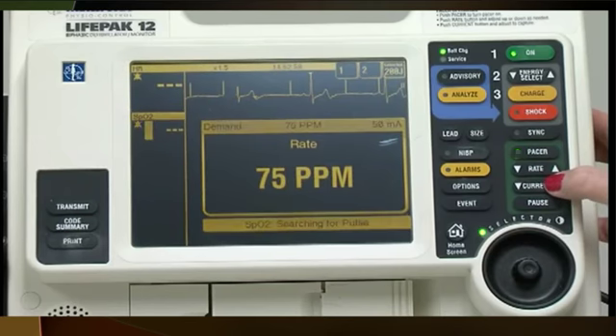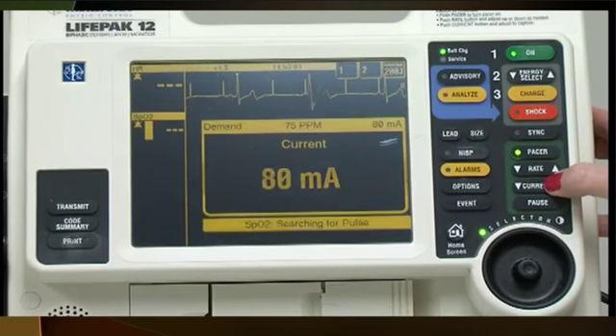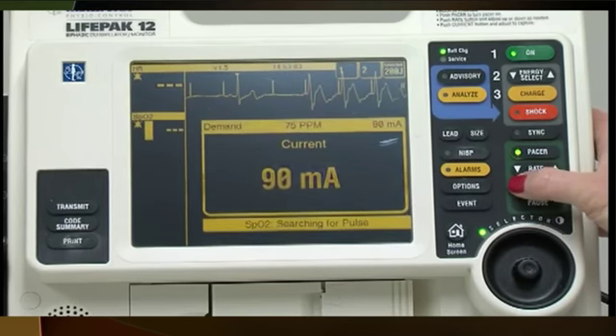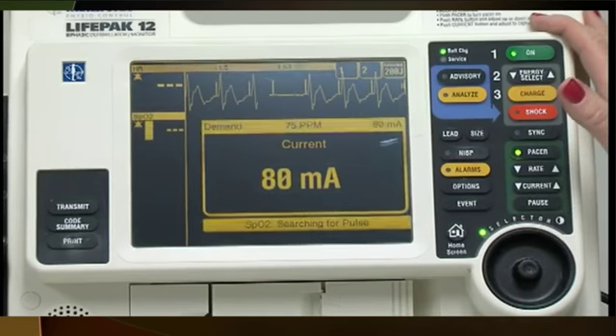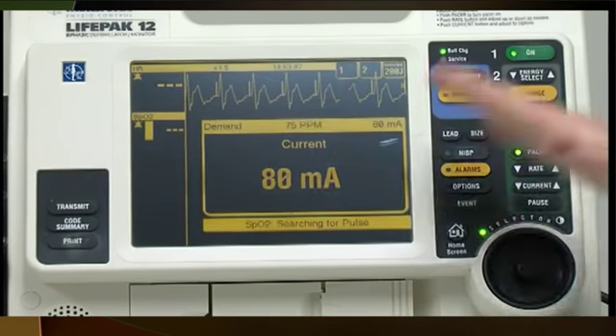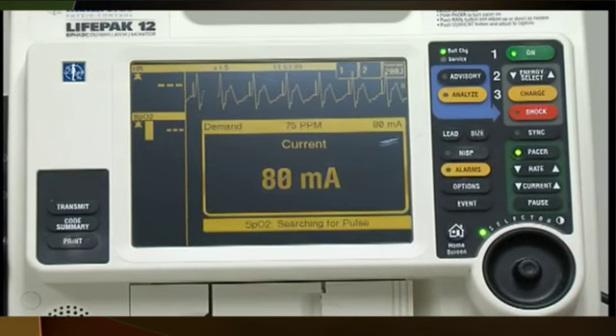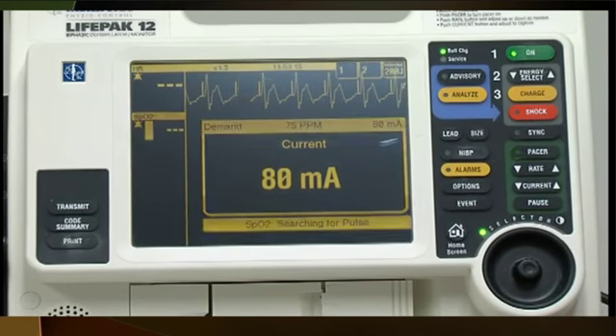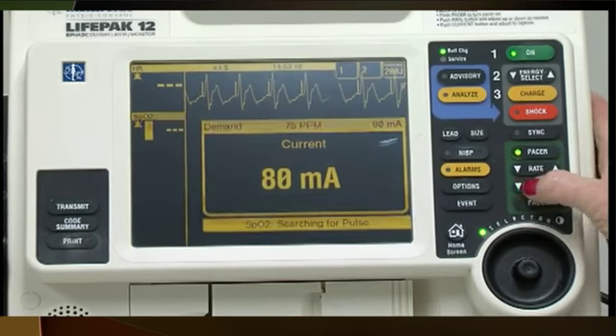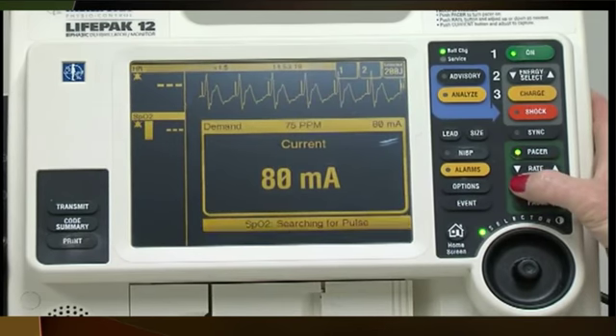With this stimulation, I need to increase my milliamps to get that 1-to-1 capture, due to this being an external machine. I now have one-to-one capture, and that is by increasing my milliamps. To be able to do your stimulation threshold, I now need to decrease my milliamps until I lose that one-to-one capture.